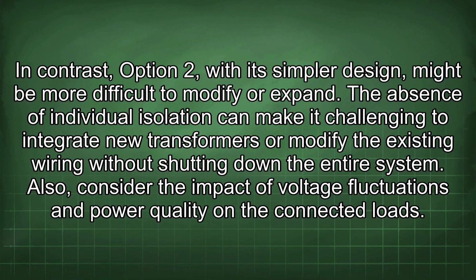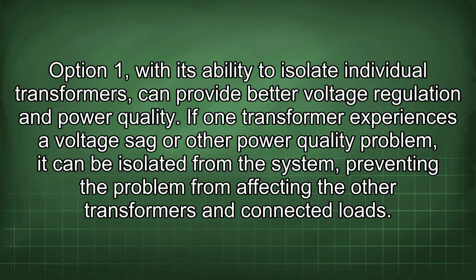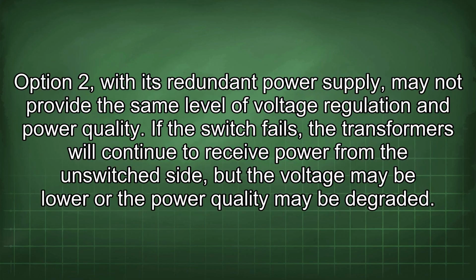Also, consider the impact of voltage fluctuations and power quality on the connected loads. Option 1, with its ability to isolate individual transformers, can provide better voltage regulation and power quality. If one transformer experiences a voltage sag or other power quality problem, it can be isolated from the system, preventing the problem from affecting the other transformers and connected loads. Option 2, with its redundant power supply, may not provide the same level of voltage regulation and power quality. If the switch fails, the transformers will continue to receive power from the unswitched side, but the voltage may be lower or the power quality may be degraded.